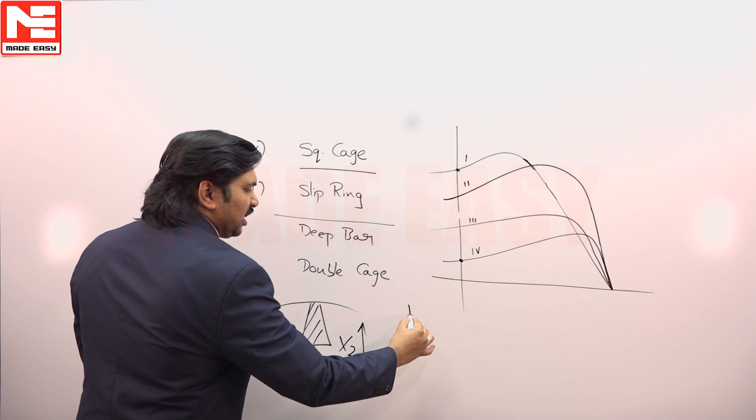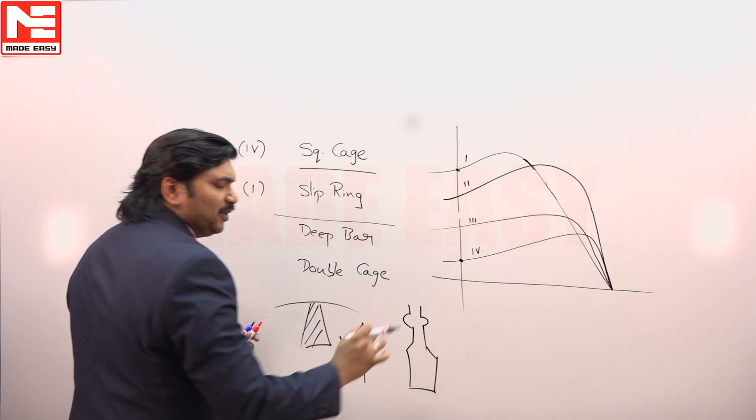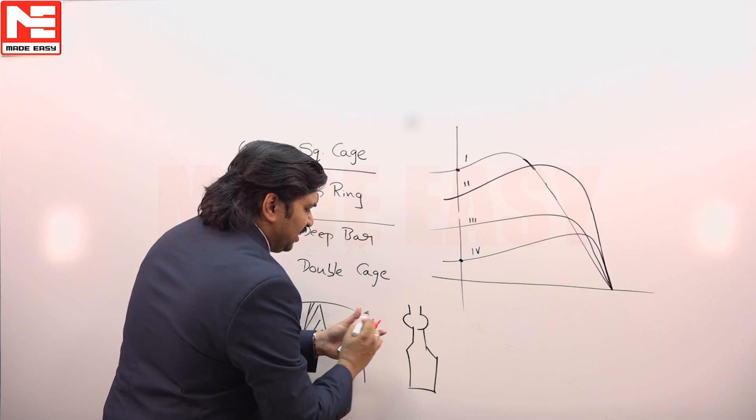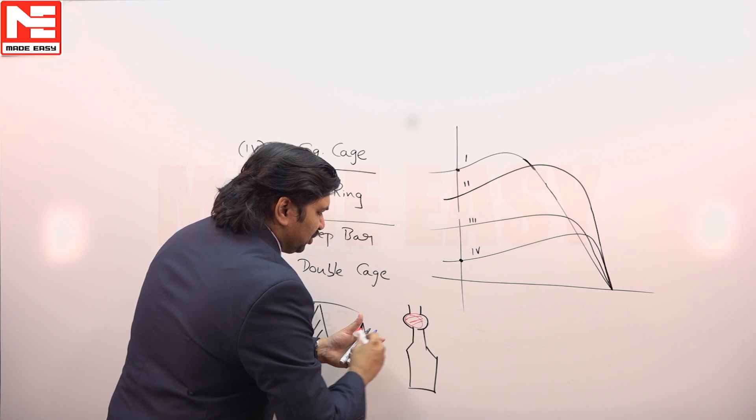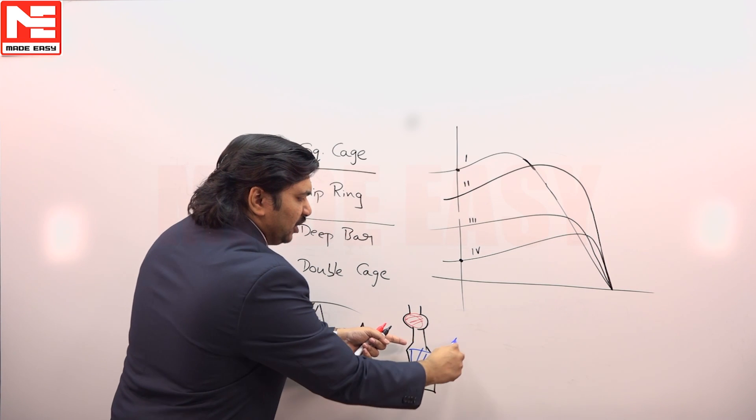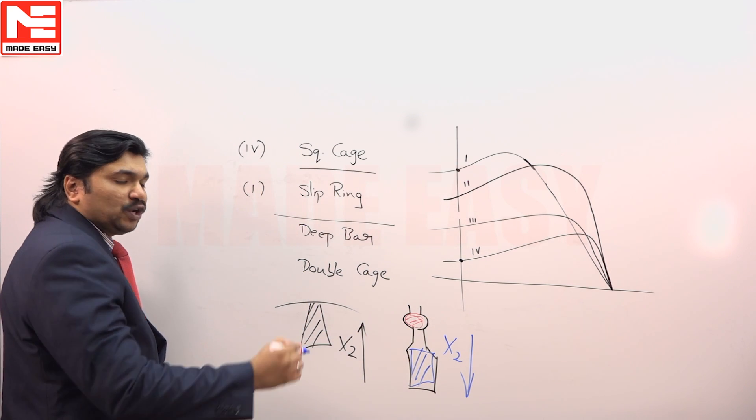Double cage is not like that. Double cage has two cages with an air gap in between. This air gap will definitely create between outer cage and inner cage. The air gap will reduce X2, because it offers reluctance to leakage in the rotor, within the rotor.